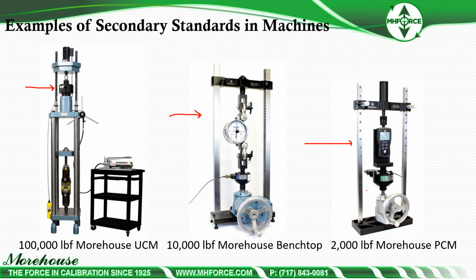All of these, you can see the load cell, all have load cells which have been calibrated by primary standards. So therefore, they can calibrate to E74 and assign a Class A range. They can also calibrate all these other devices seen in the picture: handheld force gauges, Dillon dynamometers, tension links, all of that stuff. Now, this portable machine was built for a reason, and that's ergonomic, and it's a lot easier to calibrate these handheld force gauges with this PCM in tension and compression using the proper adapters, as opposed to stacking like 250 pounds of weights and playing Jenga. So it solves a very ergonomic issue and improves the safety of technicians.